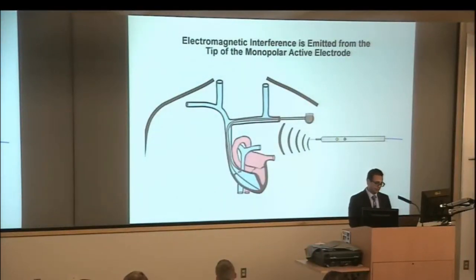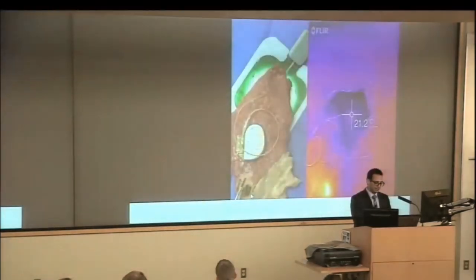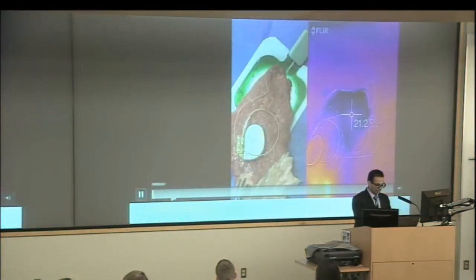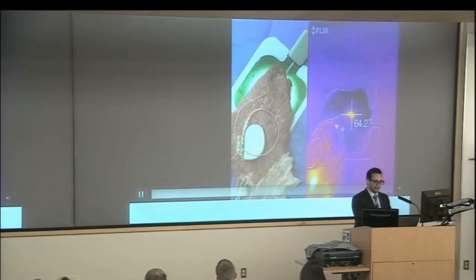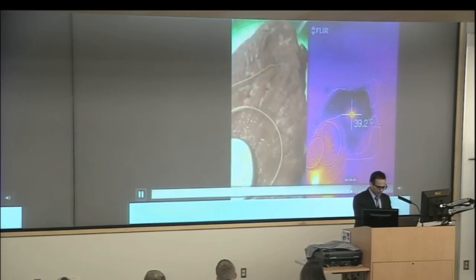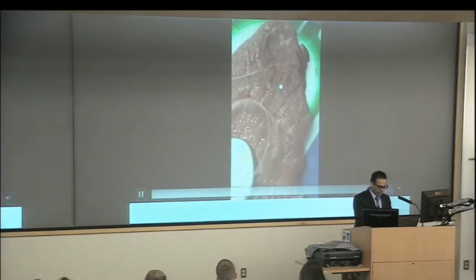It can really interfere with the function of the device. It can also induce a current in the leads and cause a thermal effect at the tissue-lead interface. This is demonstrated in this video here with a thermal camera. They're activating a monopolar device, which induces a current in this wire. At the non-insulated tip, you can see the thermal effect rising. You're reaching temperatures above 50 degrees, which can cause cell death. When they remove this, you can see that it's caused a burn injury.